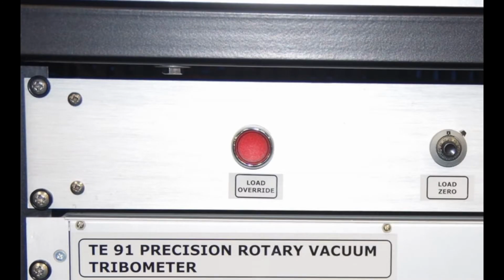A switch on the front of the signal box is used to enable and disable the loading system. When the load system is active, the switch is illuminated. If the switch is then pressed, the load system is disabled and the light is turned off. A pressure switch is fitted to the air supply for the loading system. If the pressure is too low, the switch is triggered, an indicator is illuminated, and the loading system is disabled.